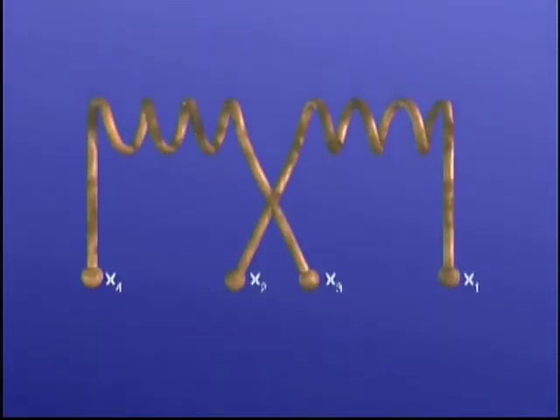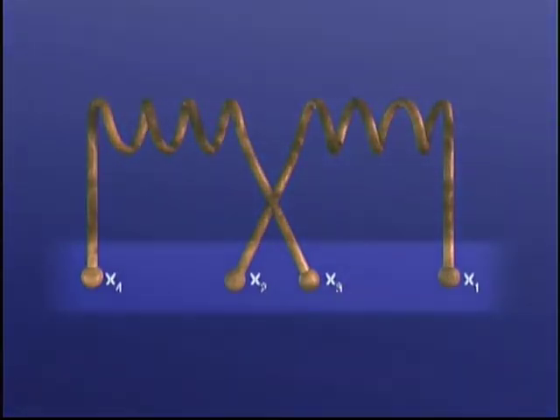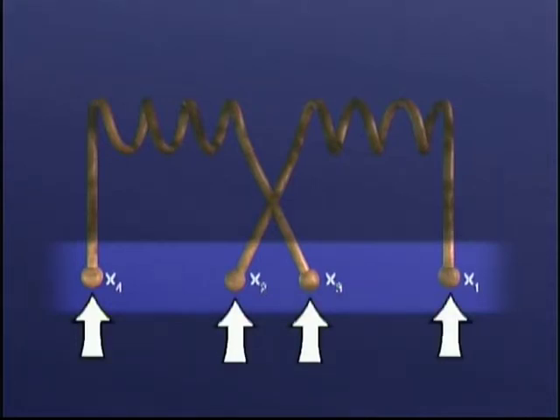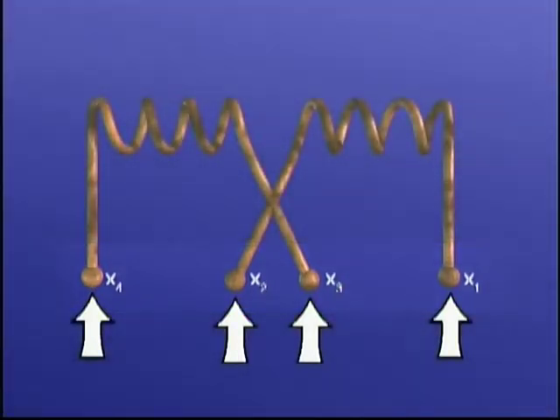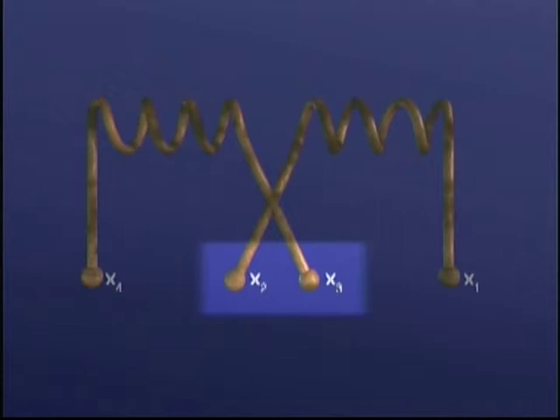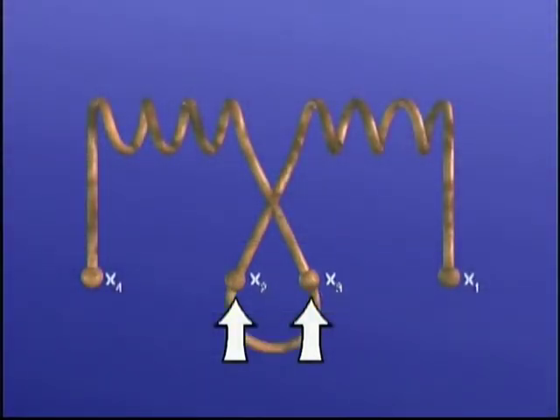Another thing you should realize about the example that we demonstrated is that some transformers have 4 secondary bushings instead of 3. On transformers with 4 bushing arrangements, the ends of the two coils that make up the secondary winding are each connected internally to a separate secondary bushing. This design provides the flexibility of changing the wiring of the secondary winding without having to go inside the transformer to change connections. To connect the secondary winding of this transformer in a conventional manner, the X2 and X3 bushings, which are connected to the ends of separate coils, are joined together by a metal strap or jumper.